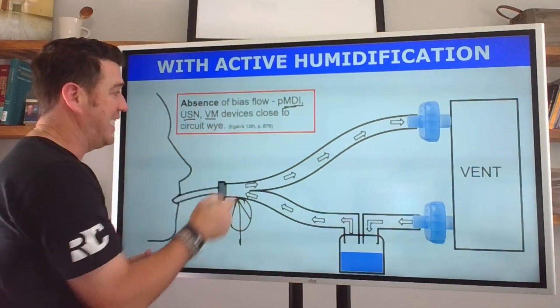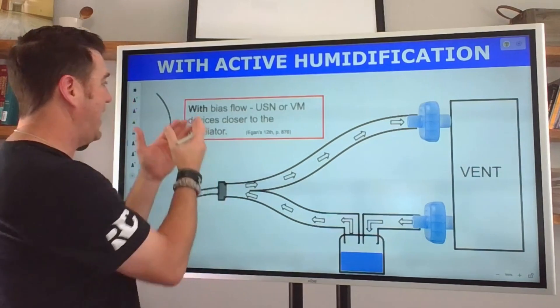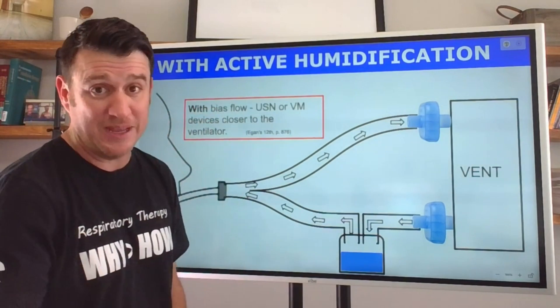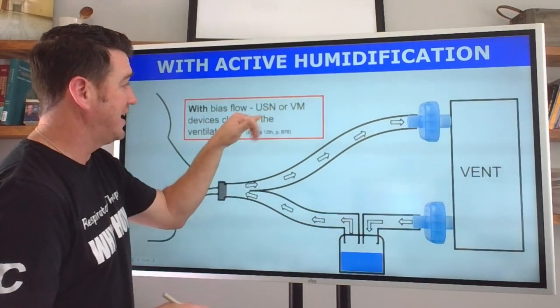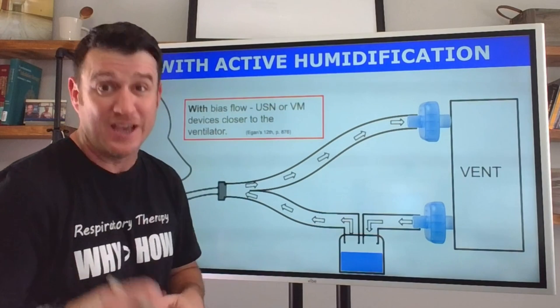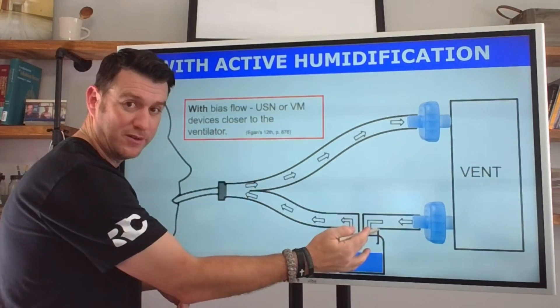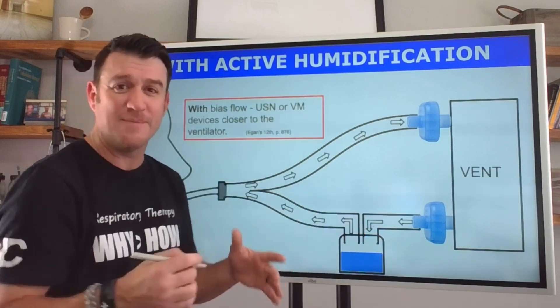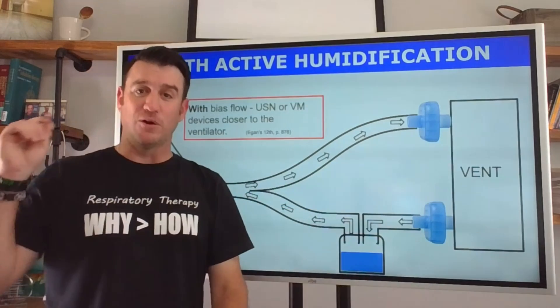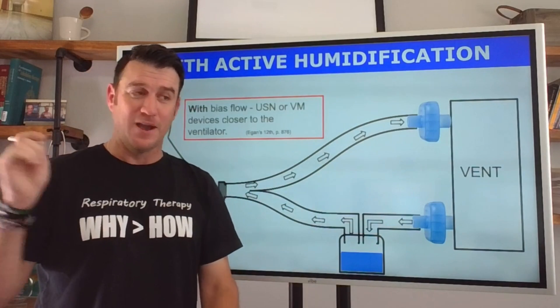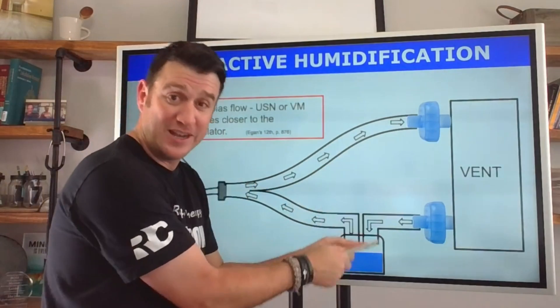What about if we have bias flow? What's recommended that showed the greatest level of deposition was an ultrasonic nebulizer or a vibrating mesh device closer to the ventilator. Without bias flow we're going closer to the patient but with bias flow we're going closer to the ventilator.